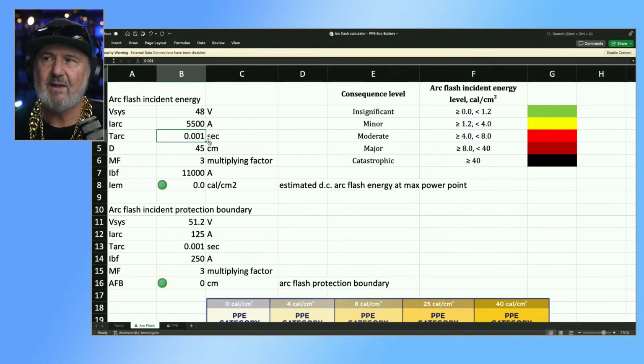Now the arcing time, it says if there is no string overcurrent protection within the string of cells, or in the case of lead acid battery, the actual battery cells, then you use 2 seconds of arcing time. And then you need to put in what the working distance is. Now, working distance is deemed to be arm's length, 45 centimetres, unless you're using a robot or something.